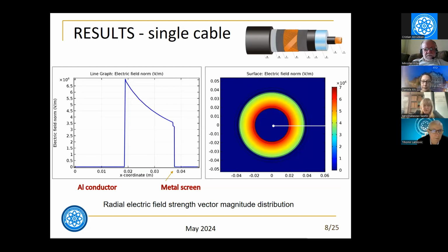In this picture, we wish to show the distribution of the electric field, and we can see the dependence of the radial electric field strength vector magnitude on the distance from the single high voltage cable axis. As could be expected, inside the cable conductor, including the conductor's boundary, the magnitude of the electric field strength vector is 0. As you can see, here it is 0. Outside the conductor, the magnitude of the electric field strength vector increases rapidly to its maximal value.